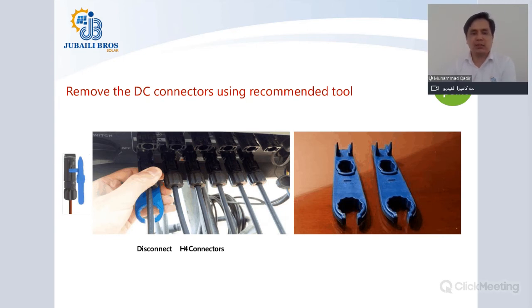Remove the DC connectors using the recommended tool. Again, the MC4 connectors should be dismantled and disconnected with the right tool. The tool which is used for tightening can normally be used for disconnection as well. Similarly, for the Helios H4 Amphenol connectors, you should be using the right tool for disconnection as well. Again, the tool from Amphenol can be used for both connection and disconnection.